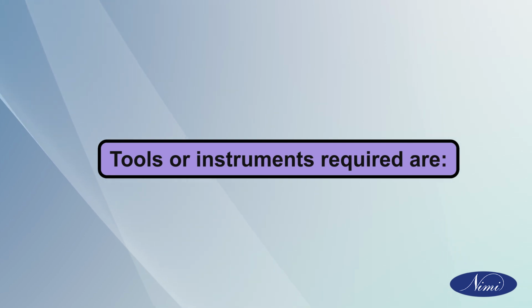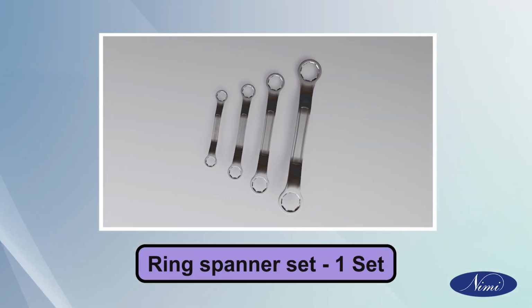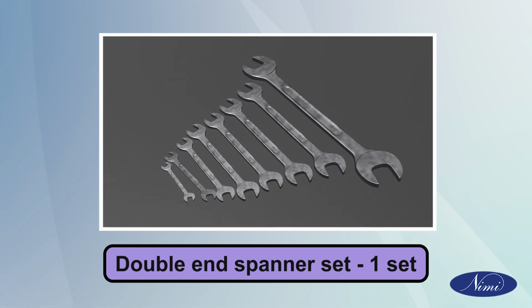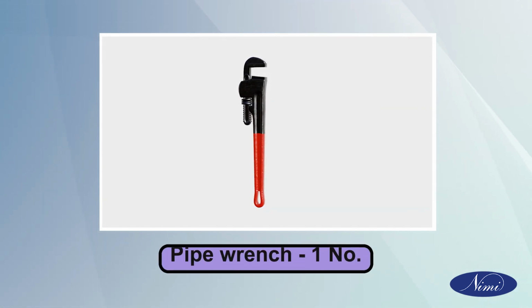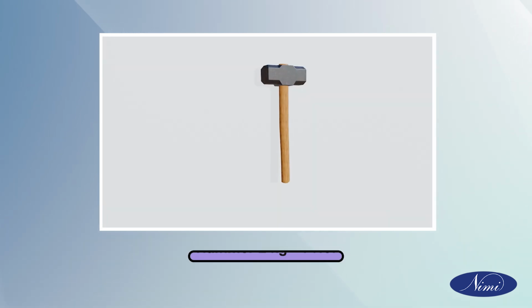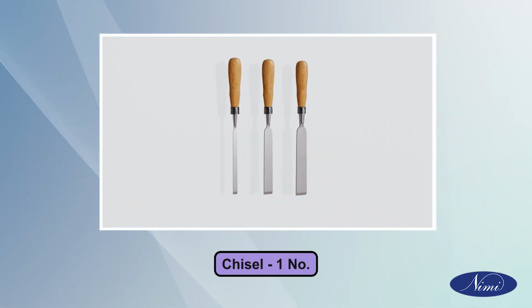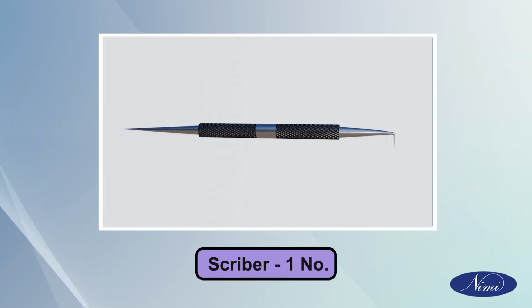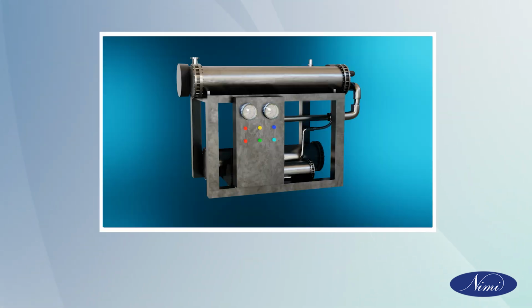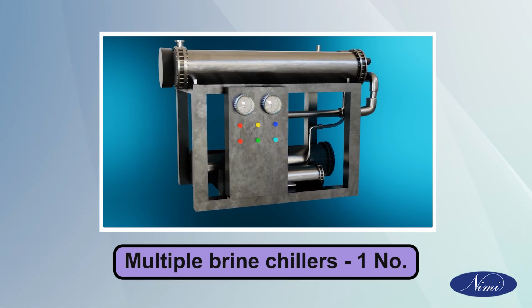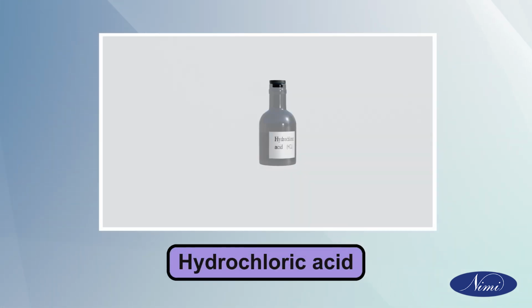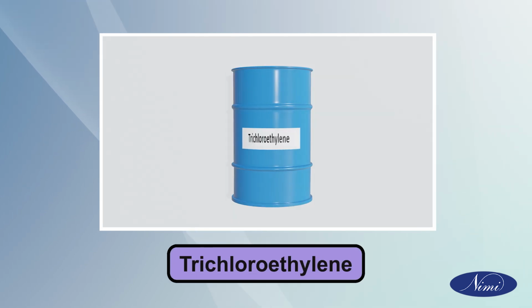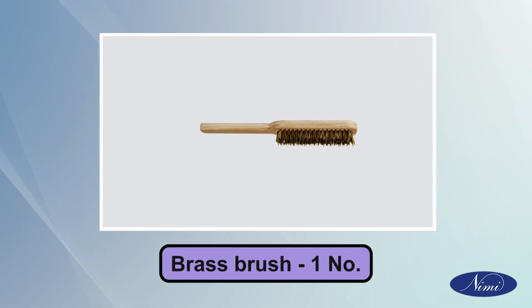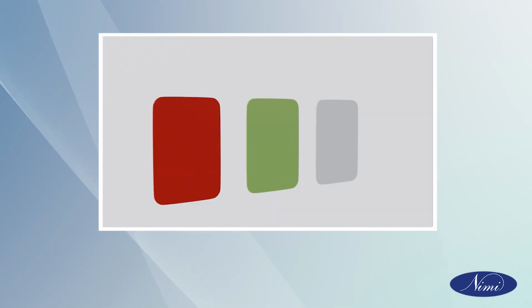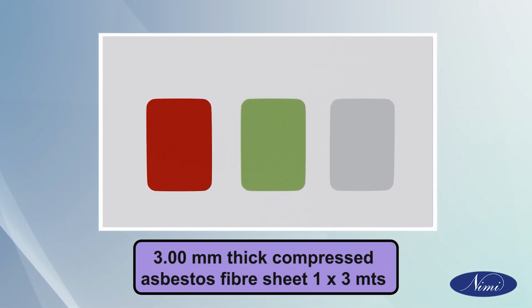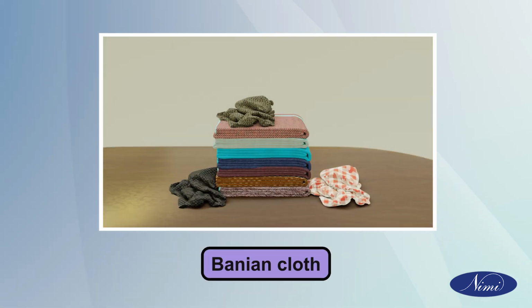Tools or instruments required are ring spanner set 1 set, double end spanner set 1 set, pipe wrench 1 number, screw spanner 1 number, hammer 2 kg 1 number, chisel 1 number, scriber 1 number. Equipment required: multiple brine chillers 1 number. Materials required: hydrochloric acid, trichloroethylene, brass brush 1 number, brass scrubber 1 number, 3 mm thick compressed asbestos fiber sheet 1 into 3 meters, banian cloth.